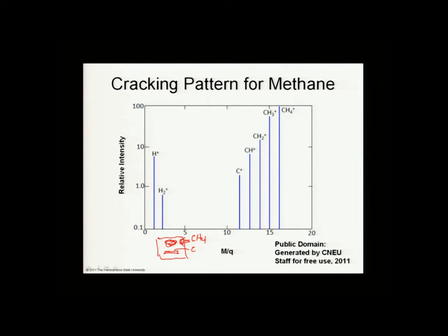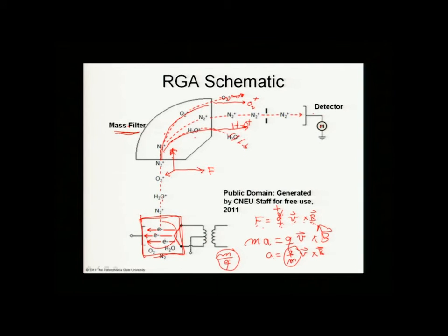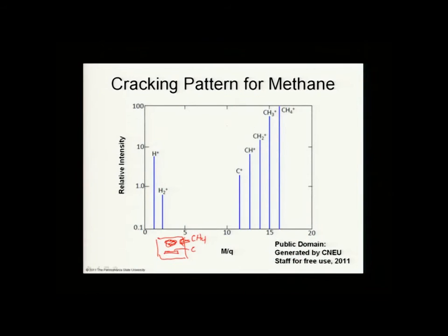Especially if you're trying to get high yield, you have to know exactly what's going on in the process. So we're trying to find out exactly what's flying around in here. And by using this mass filter, we're able to scan across here. You can see what we're doing is changing the magnetic field. And we're scanning across here and we can find out, oh wow, there's hydrogen present. Actually, there's H2 ions present also. There's carbon ions present. There are carbon hydrogen ions, carbon with two hydrogens, carbon with three hydrogens.